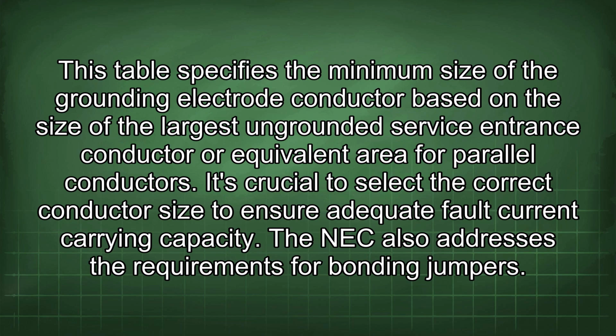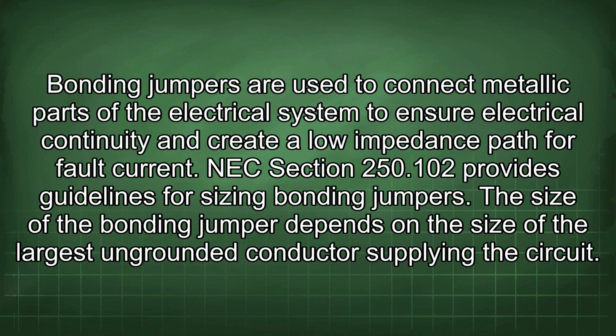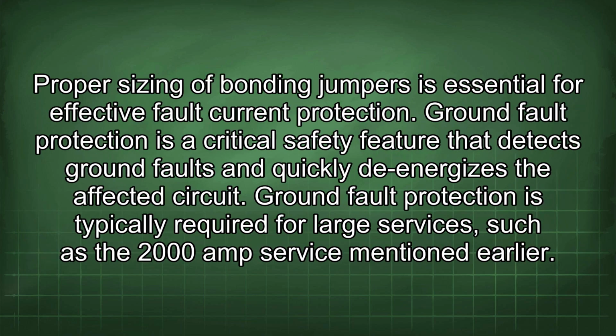The NEC also addresses the requirements for bonding jumpers. Bonding jumpers are used to connect metallic parts of the electrical system to ensure electrical continuity and create a low impedance path for fault current. NEC Section 250.102 provides guidelines for sizing bonding jumpers. The size of the bonding jumper depends on the size of the largest ungrounded conductor supplying the circuit. Proper sizing of bonding jumpers is essential for effective fault current protection.